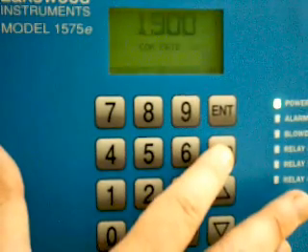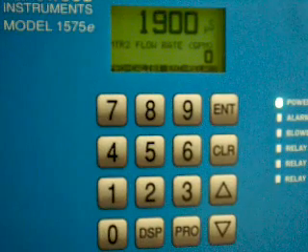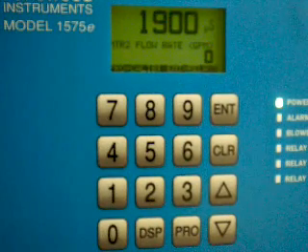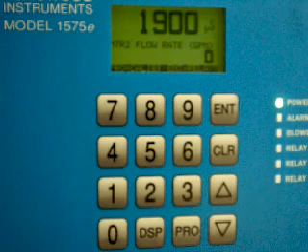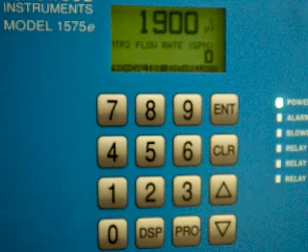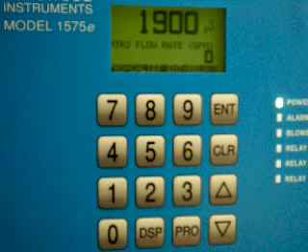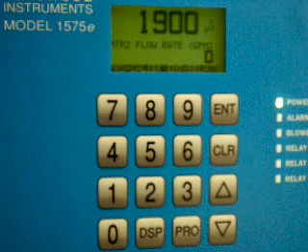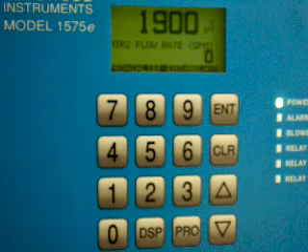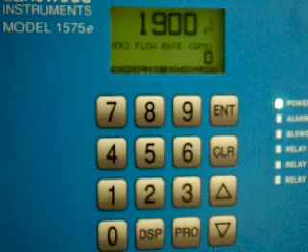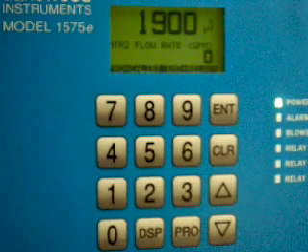It says the calibration is now complete. Now what you want to do then is go ahead and monitor that reading for a few minutes and see if it's wandering around. And in the next day or so, I would come back and check it again. If the calibration doesn't seem to hold, you can call Lakewood Instruments and we can run you through a few of the troubleshooting procedures, and they're relatively simple, and give you some places to look at in the system that may cause the reading to wander, because typically the instrument's really solid as far as the calibration and holding the calibration, and it's a system issue that causes the wandering.